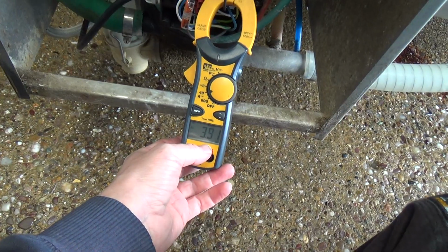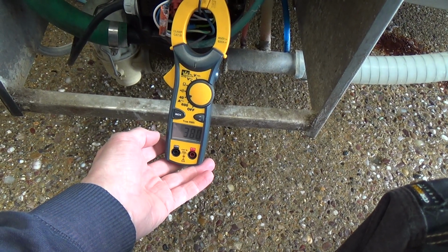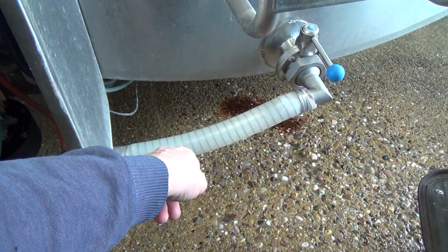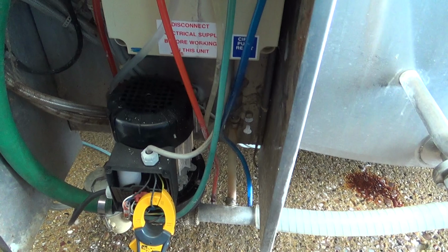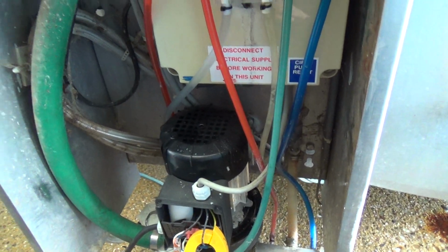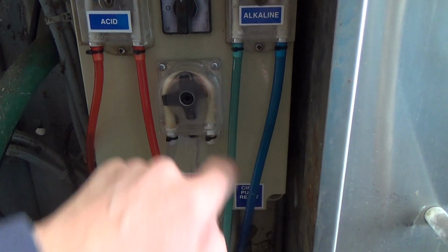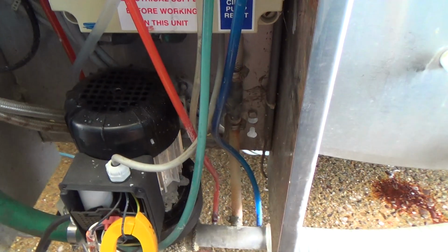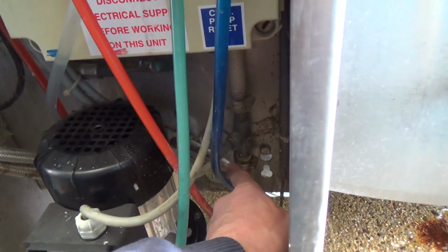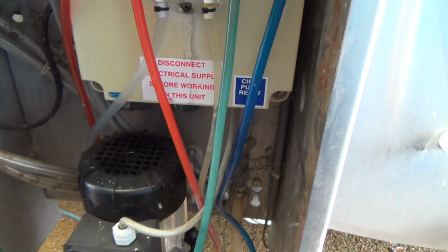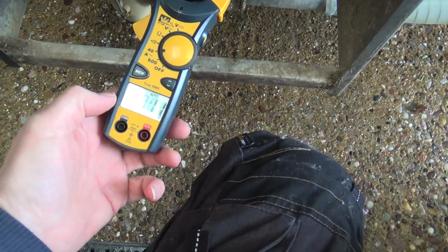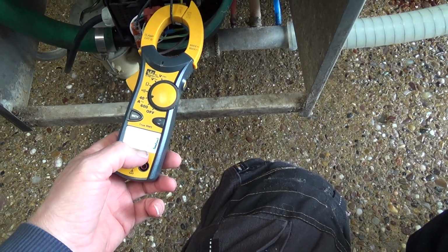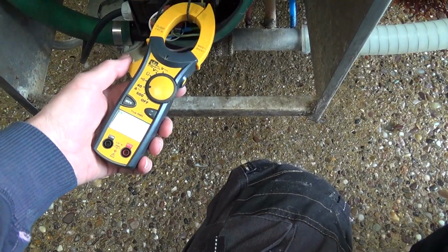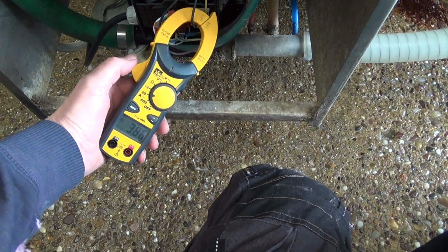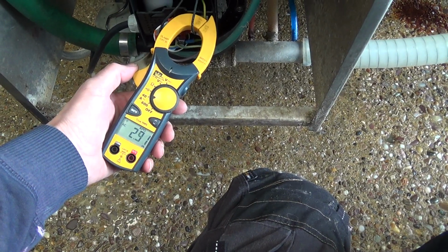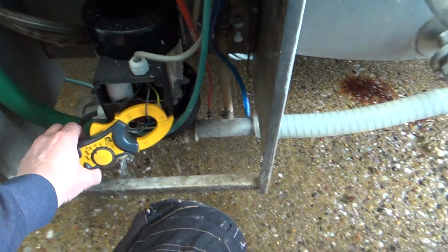It's running up and down, depends how much air bubbles are in there. So that hypo pump's not working too well, I think the tube's come loose. We'll have to check, that might be why this is all corroded. We'll have to check that connection there is there. Basically running about up to its maximum. Although, you know, you can move this about, it'll change slightly. So I don't think the problem is the pump.